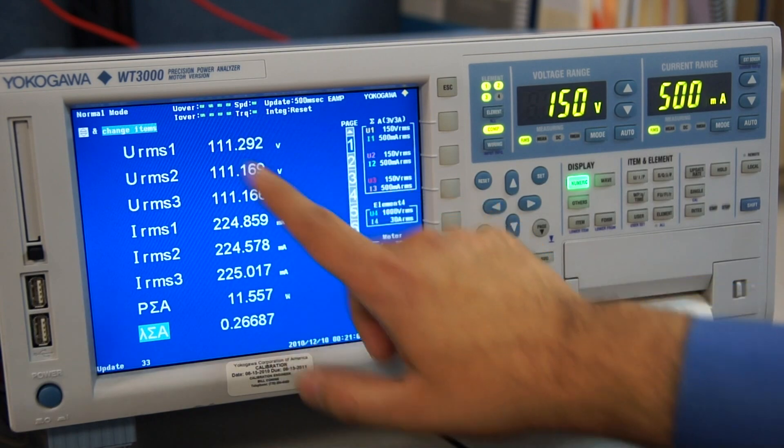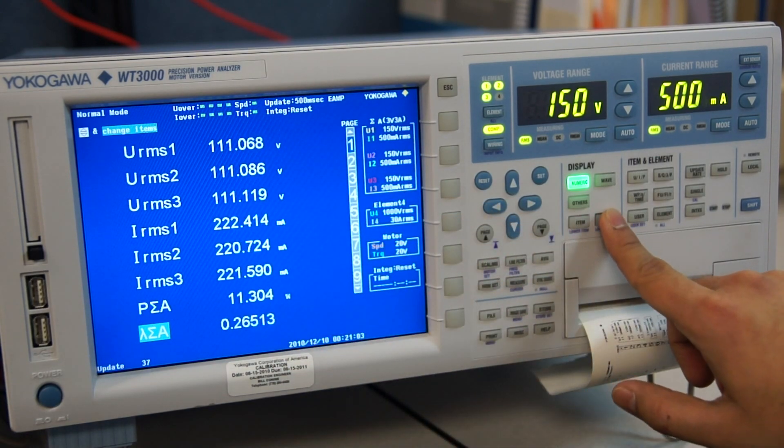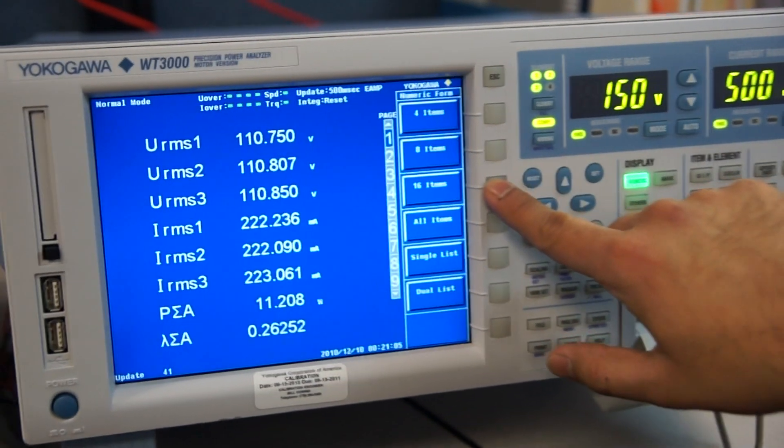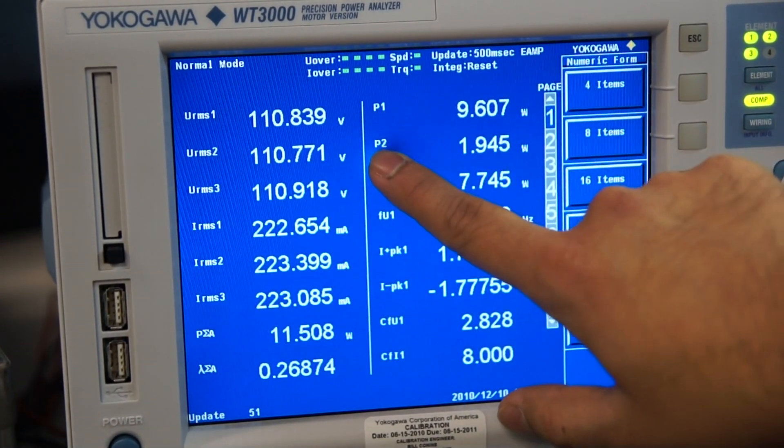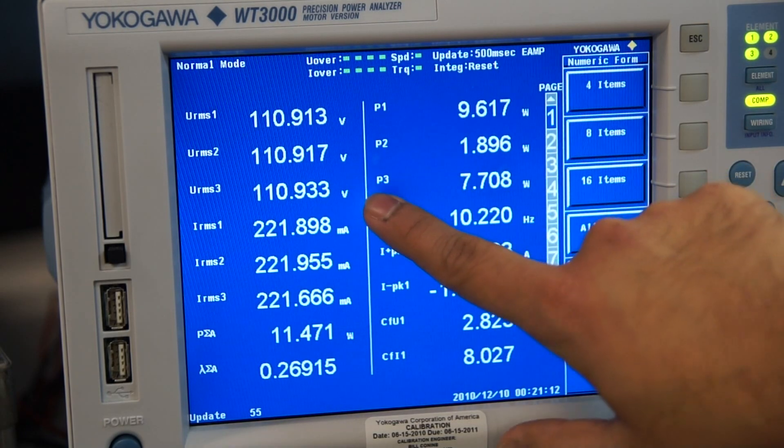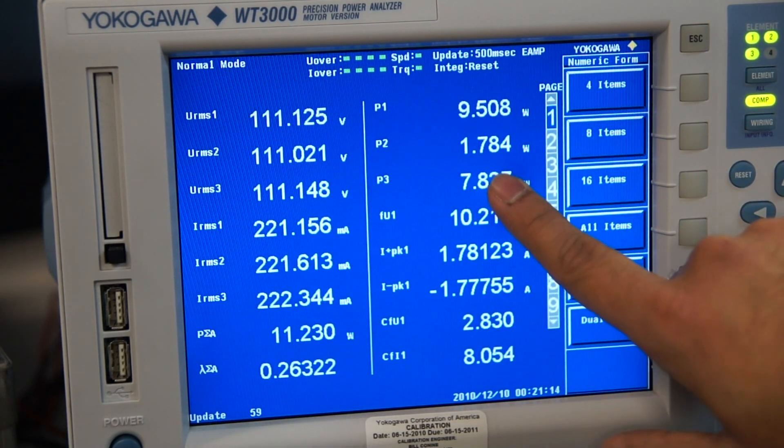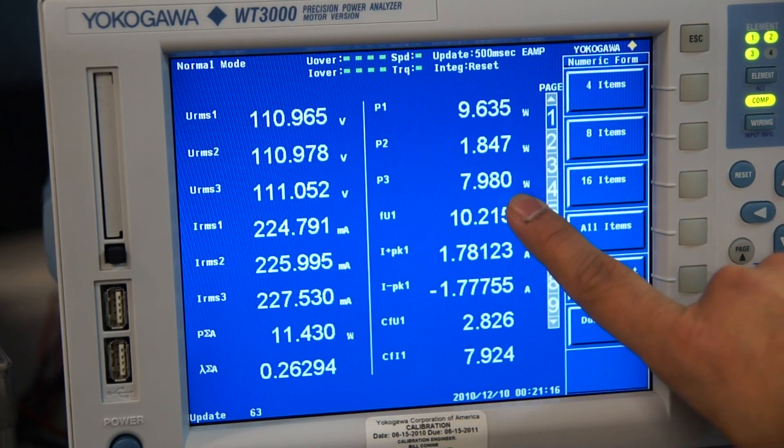Let's also verify that the individual phase powers are correct, so that way we can tell that the wiring is correct. You can see that phase one power is positive. Phase two power is also positive. And so is phase three power. That's the first thing that tells you that your wiring is correct.